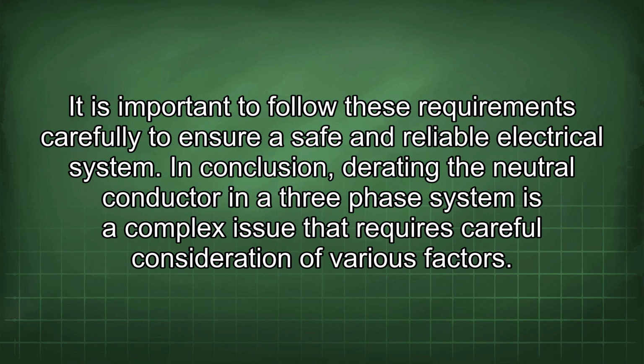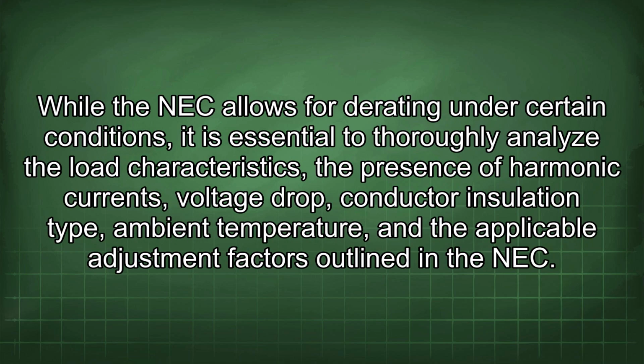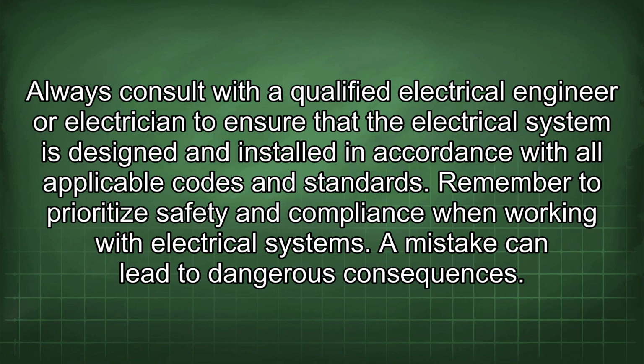In conclusion, derating the neutral conductor in a three-phase system is a complex issue that requires careful consideration of various factors. While the NEC allows for derating under certain conditions, it is essential to thoroughly analyze the load characteristics, the presence of harmonic currents, voltage drop, conductor insulation type, ambient temperature, and the applicable adjustment factors outlined in the NEC. Always consult with a qualified electrical engineer or electrician to ensure that the electrical system is designed and installed in accordance with all applicable codes and standards.